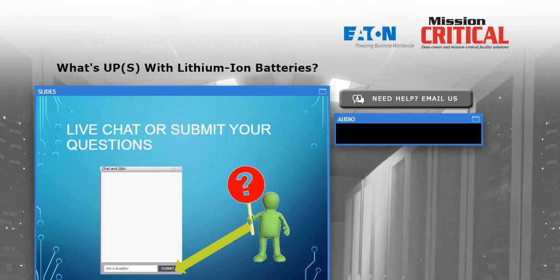And again, keep in mind, we haven't seen the final version of the IFC code, but what the preliminary version indicates is that if I have a given enclosure that is less than 70 kilowatt hours, I don't have to maintain those space limits. And fortunately, most of the lithium batteries that we've seen for this application are in the low to mid 30s kilowatt hours, so it's okay to put them side by side, back to back up against the wall, etc.